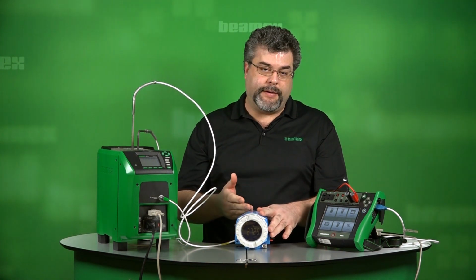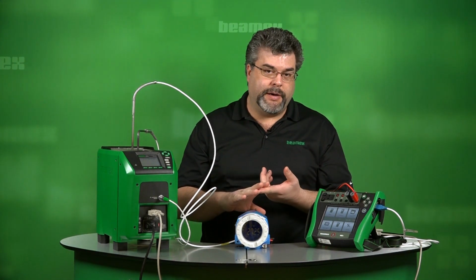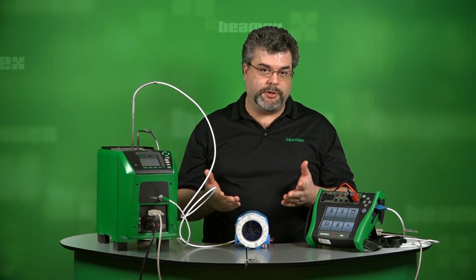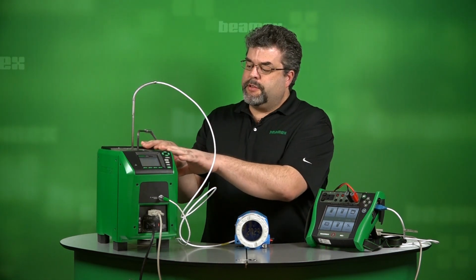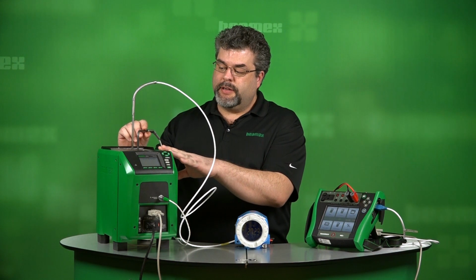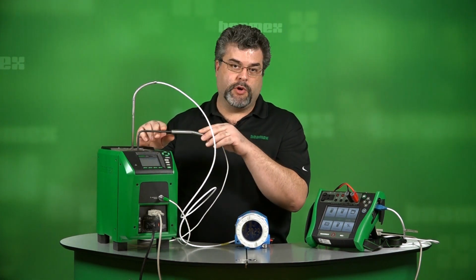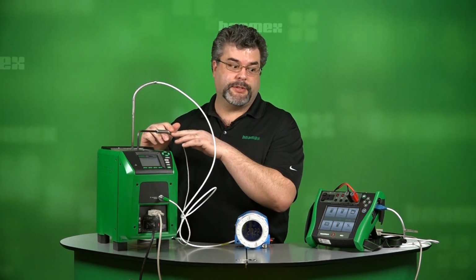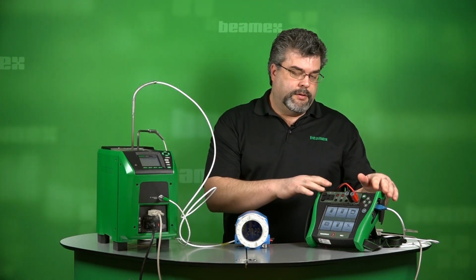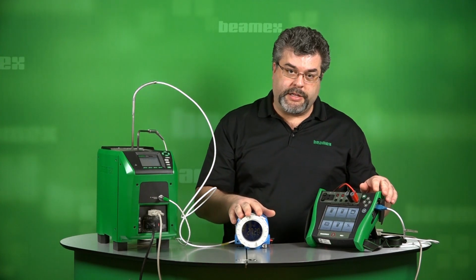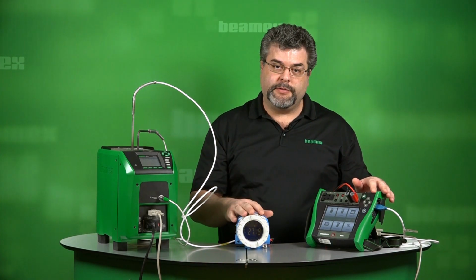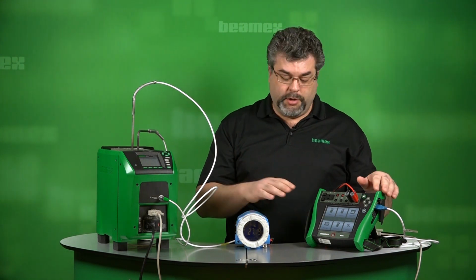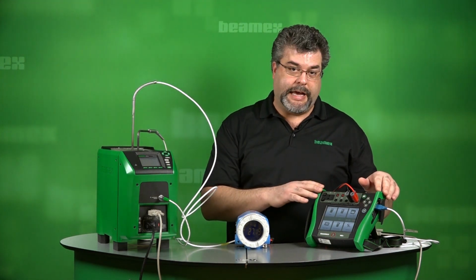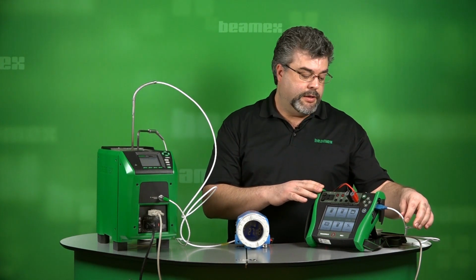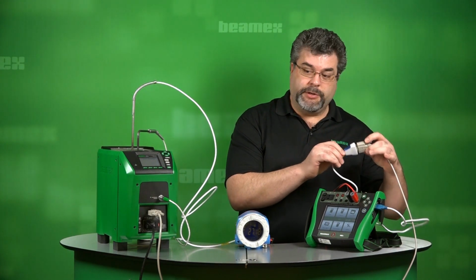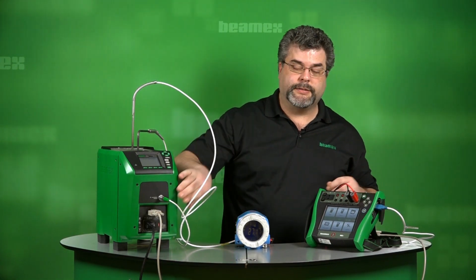This one happens to be a Foundation Fieldbus, but it could easily be a Profibus or a Hart or even a standard conventional transmitter. Now the dry block, we've added an RPRT, a highly accurate temperature probe, to increase our accuracy by about 10 times. The calibrator is providing loop power to our transmitter as well as measuring our Foundation Fieldbus signal. We're controlling the dry block with our MC6 calibrator using this USB cable. The USB is going through a converter to a serial cable connecting to the front of the dry block.